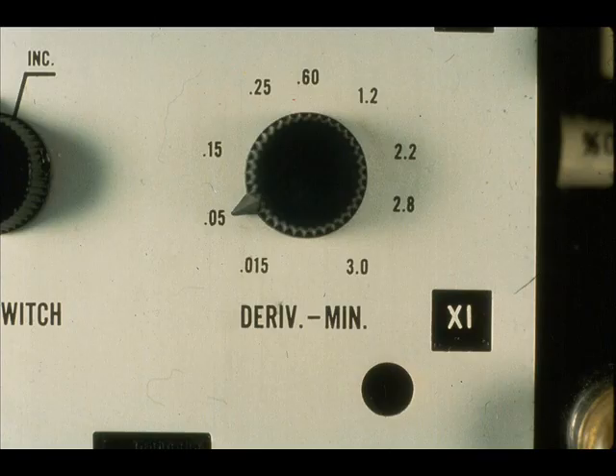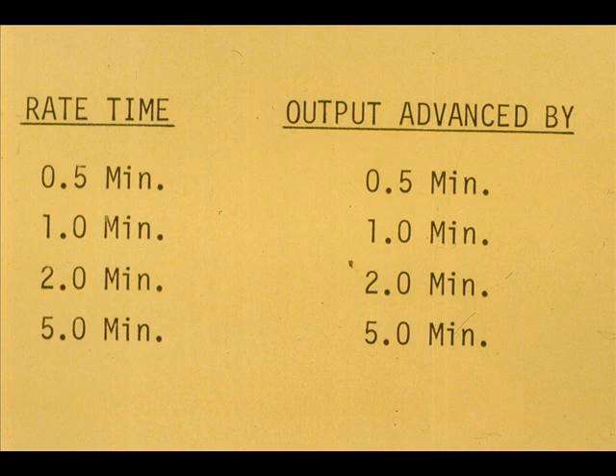Rate or derivative time is measured in minutes. A rate time of one minute means the controller output is advanced one minute ahead of what it would be with proportional action only.